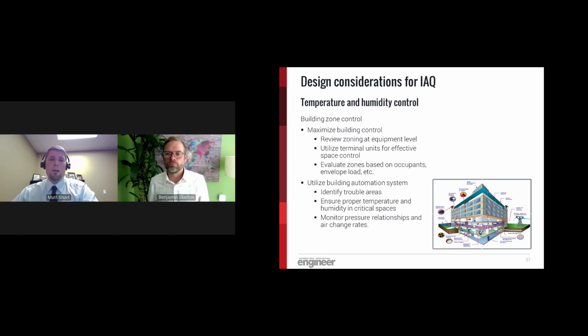With some proper programming, the system can help identify the trouble areas that we discussed earlier. The system can ensure and record temperature and humidity levels for critical spaces. It can monitor and record air changes, pressure relationships, and for some critical spaces, respond and correct some of these deficiencies.